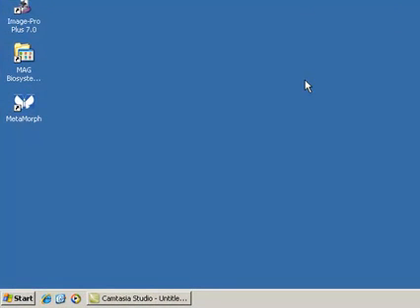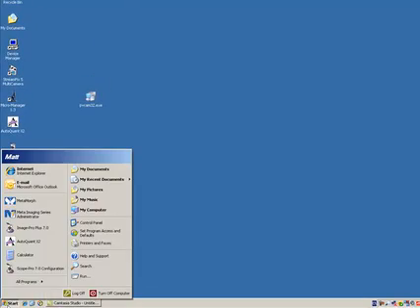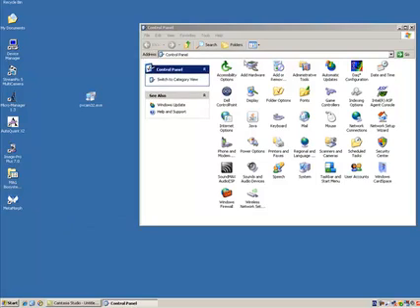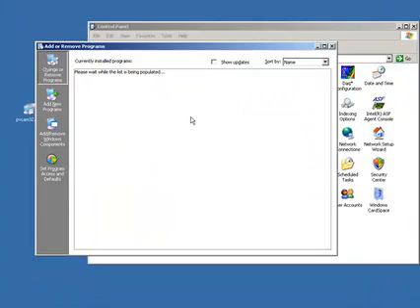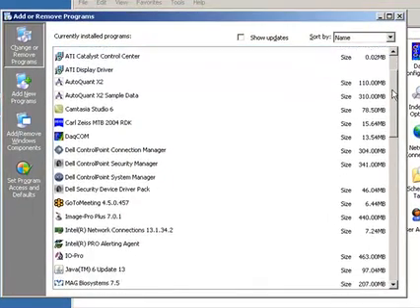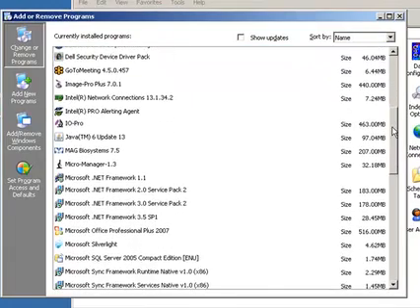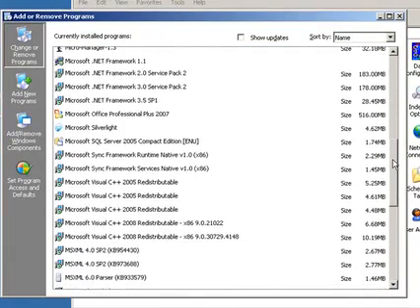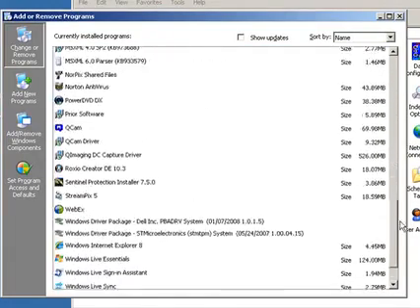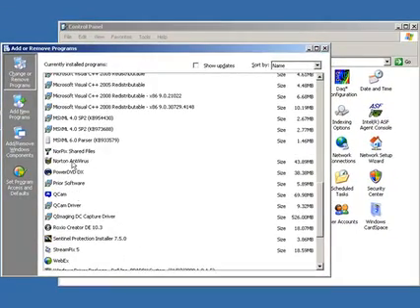Hi, this is a quick movie taking you through how to set up the Princeton Instruments Pro-EM EMCCD camera inside Metamorph. The first thing to do when you're looking to set up this camera is to make sure there are no current copies of PVcam installed on the system. This is because the Photometrics cameras use Photometrics PVcam and the Princeton Instrument cameras use PI PVcam, so Princeton Instruments PVcam.